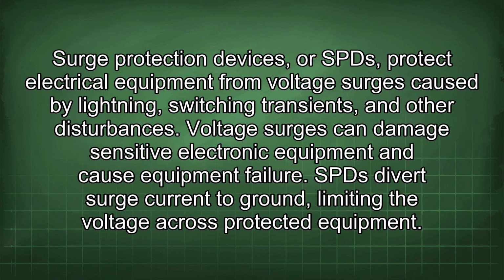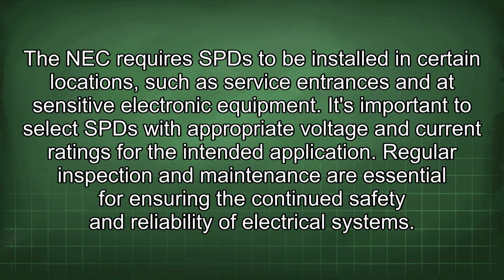Surge protection devices, or SPDs, protect electrical equipment from voltage surges caused by lightning, switching transients, and other disturbances. Voltage surges can damage sensitive electronic equipment and cause equipment failure. An SPD diverts surge current to ground, limiting the voltage across protected equipment. The NEC requires SPDs to be installed in certain locations, such as service entrances and at sensitive electronic equipment. It's important to select SPDs with appropriate voltage and current ratings for the intended application.